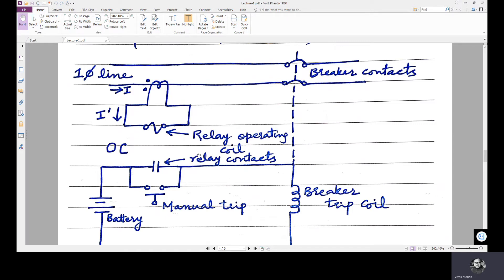The third requirement is accuracy. The instrument transformer should accurately reproduce the power system currents and voltages in the secondary, or in the operating range of the relay, over the whole operating range. The whole range of current I in the power circuit should be reproduced in the secondary.